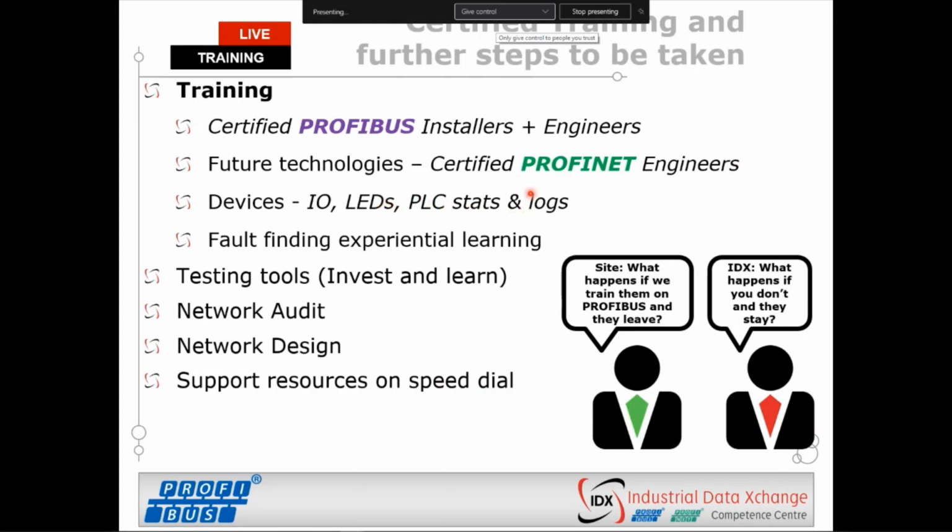that means. Statistics and logs from a PLC. From your PLC or controlling stations, it's very useful to be able to retrieve the statistics from that device, which indicates where a network might have failed. It helps you to dial down into what an issue might be. My first step walking onto a site would be, do you guys have a history of what the faults might be occurring?